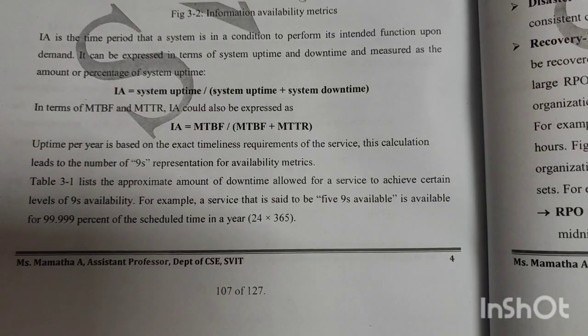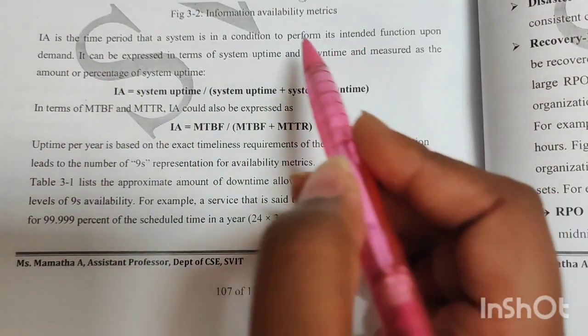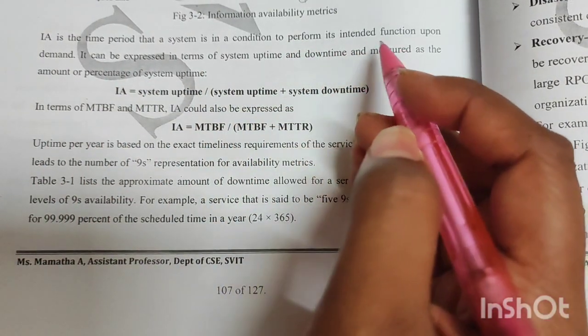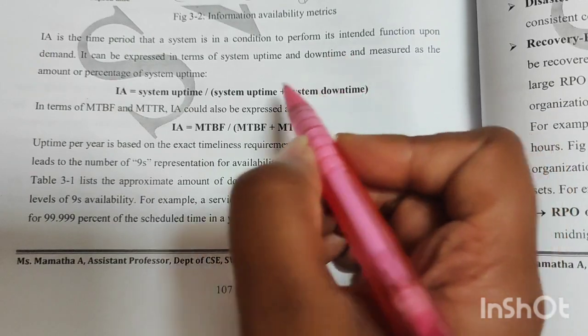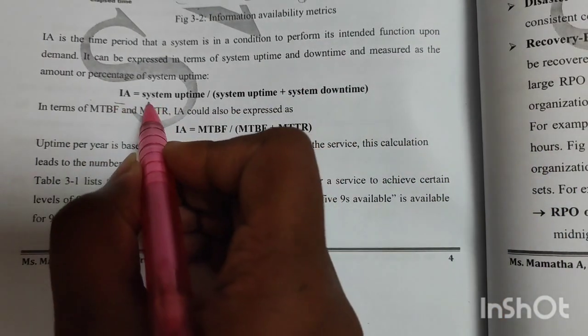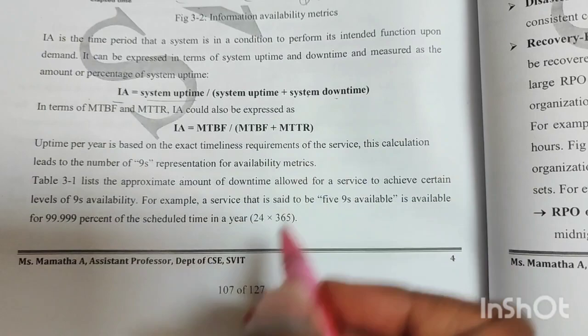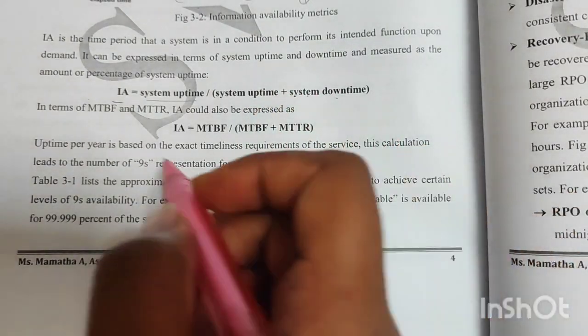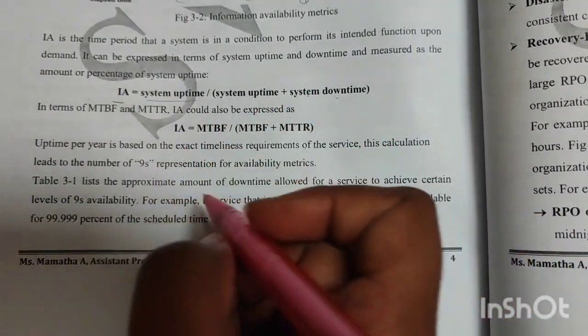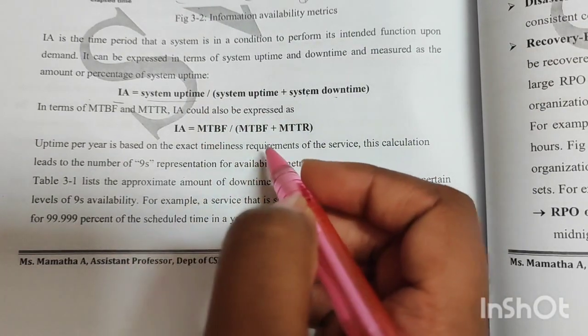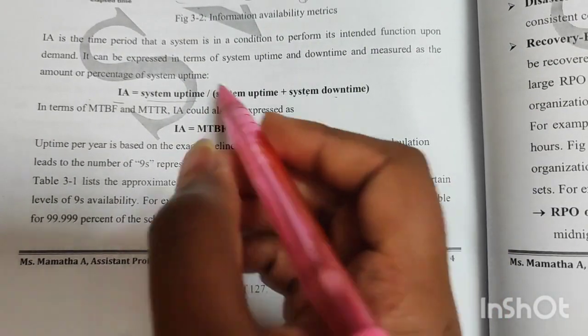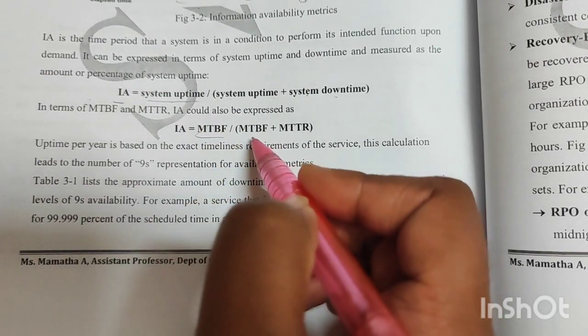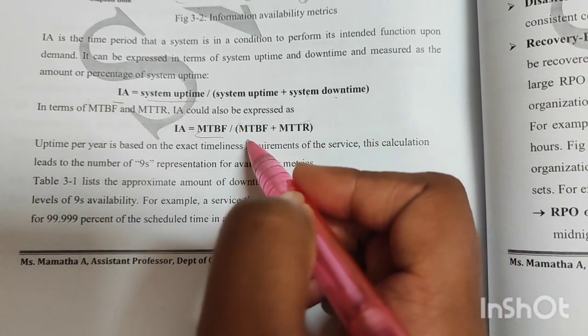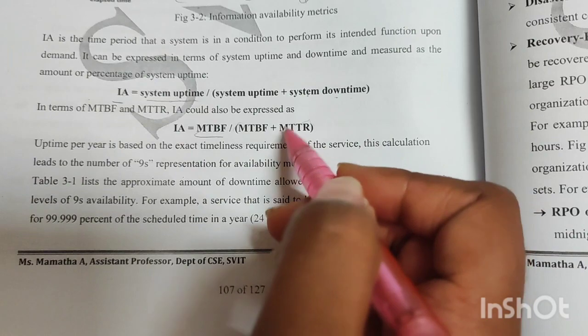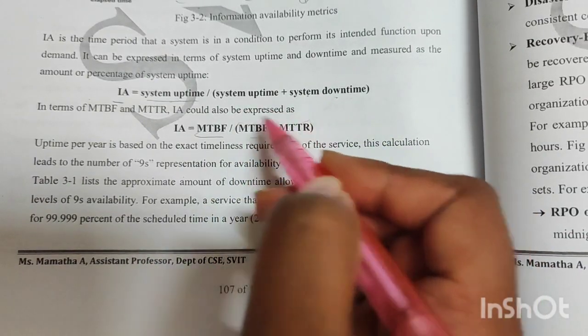Your information availability is the time period the system is in the condition that is performed. Information availability is system uptime divided by system uptime plus system downtime, which is your total system time. You can use this in terms of MTBF or MTTR. Uptime is nothing but your MTBF, and downtime is nothing but your MTTR. So you add them both and give the total.